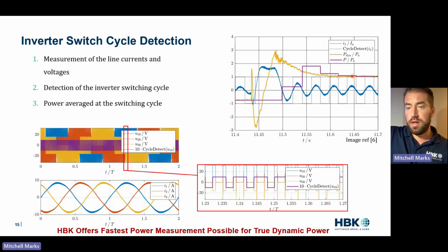And we also see that it misses a lot of the dynamics. What is happening right here? Well, my yellow trace is switch-based. We can see that power inrush. We can see how the motor control handles that power flow, and we can see that average out to the same value, but we get all those dynamics. So you might say, what's the accuracy? We're working on it. But it's super dynamic, and where we miss a lot of things with the cycle detection in the transient, we catch that with the dynamic power measurement.